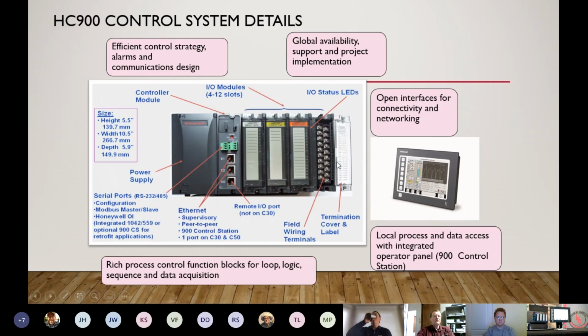So when we take a look at the hardware architecture of a HC900, let's go through this real quick to describe a little bit about what's in the rack and some of the options. At the very left-hand side of the rack, we have the power supply. This can come in 24 volts, 120 volts, 220 volt. Those are different options for the power supply. This does not take up an available slot in the rack. So slot 1 starts with the very first I/O module. It does not start with the power supply. So the first would be your power supply.